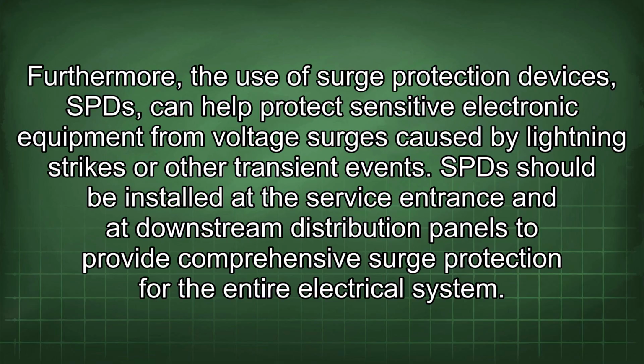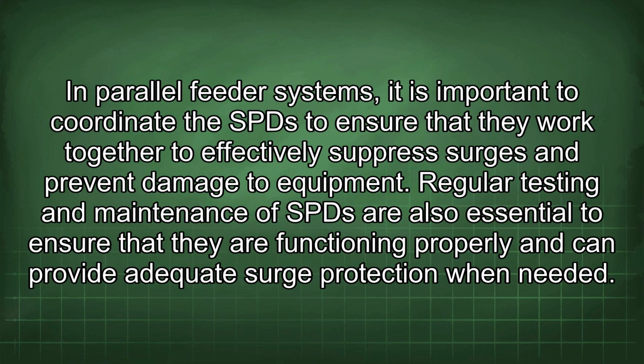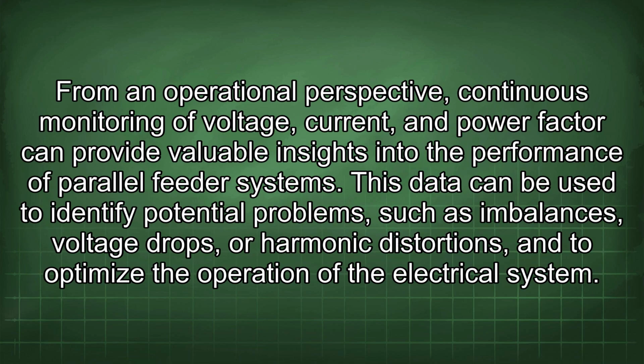SPDs should be installed at the service entrance and at downstream distribution panels to provide comprehensive surge protection for the entire electrical system. In parallel feeder systems, it is important to coordinate the SPDs to ensure that they work together to effectively suppress surges and prevent damage to equipment. Regular testing and maintenance of SPDs are also essential to ensure that they are functioning properly and can provide adequate surge protection when needed.